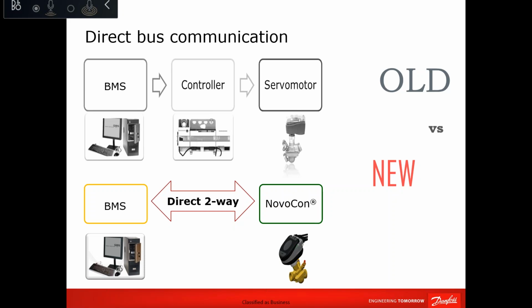So if we take normal communication in a BMS system, you have your valve, which is here at the right, with a normal gear actuator. Those are Danfoss. Then you have the controller to control the unit fan and to give the control signal. And then you have the BMS.